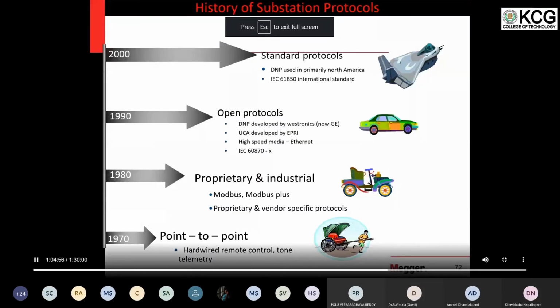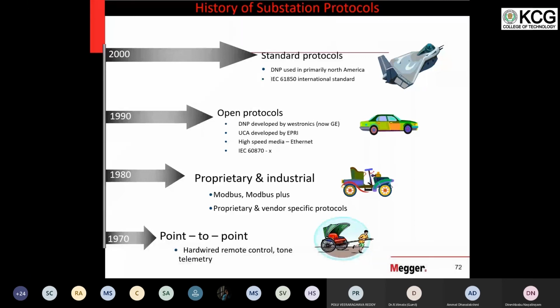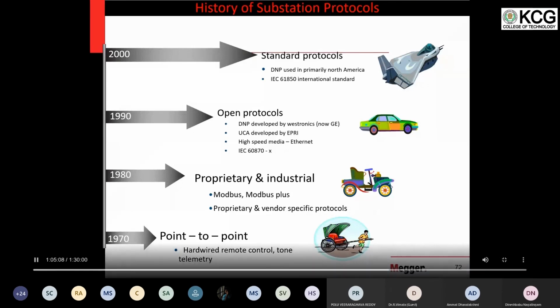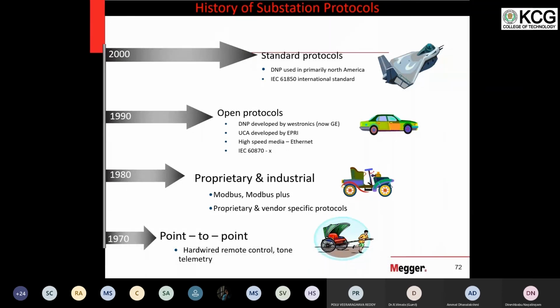You have to check in that manual what the Modbus memory map address is, the address where this current is located, and configure that current in our SCADA system. And the address will be different for voltage, frequency, everything will have a different address. Now, maybe you need 50 information points from one relay. After some time, you would move on to relay 2. It may be from another manufacturer. That relay needs another 50 information points, but all the addresses will be different. So if this continues, we will keep on working on different kinds of addresses. If you have 10 types of relays, 10 into 50, 500 addresses we need to configure.